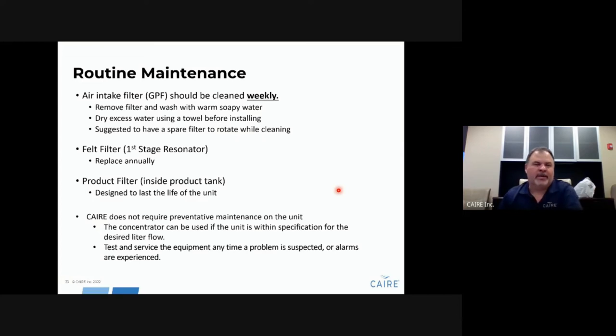For routine maintenance, the air intake filter on the back of the unit should be cleaned weekly by the user. Make sure the filter is completely dry before putting it back on — moisture should not go directly onto the control board. Once a year, replace the first-stage resonator filter. The product filter inside the unit is designed to last the life of the unit — it is a lifetime filter and does not need replacement. CAIRE does not require preventive maintenance as long as the unit is operating in spec, not alarming, and functioning normally. There is no need to work on it other than changing filters as needed.